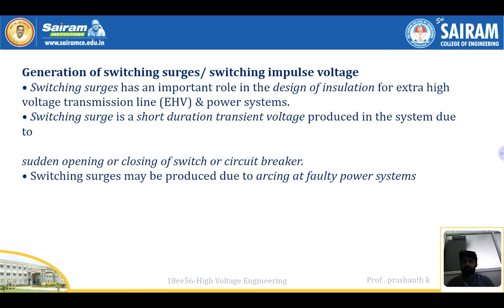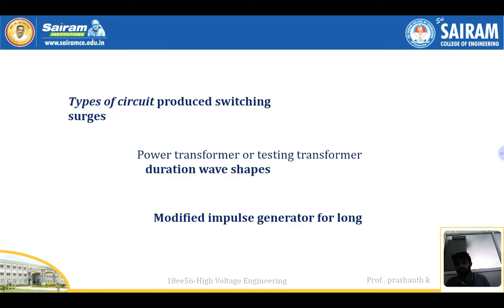For example, if you insert a plug into the socket, sometimes you get a spark, right? Sometimes you get a crackling sound also. So that spark is like a switching surge. In the high voltage area we will get more spark surges. Switching surges may be produced by the arcing of a faulty power system. If it is faulty, definitely we will get switching surges, right?